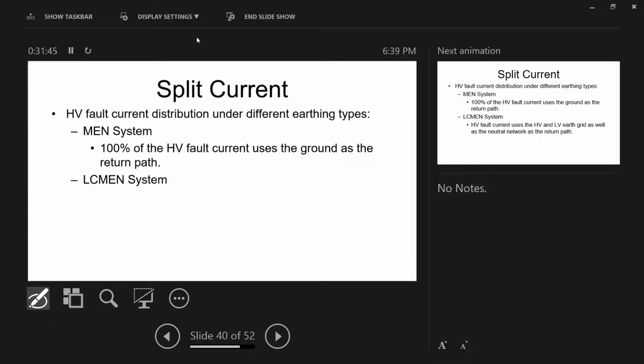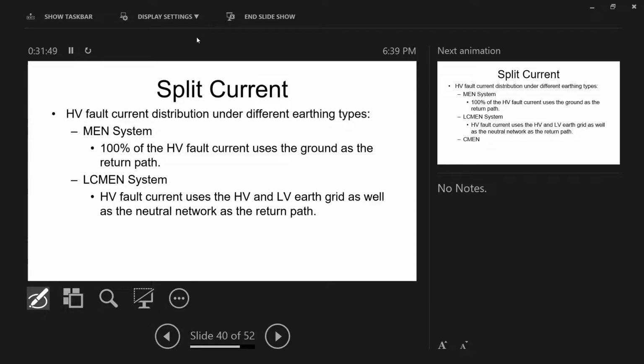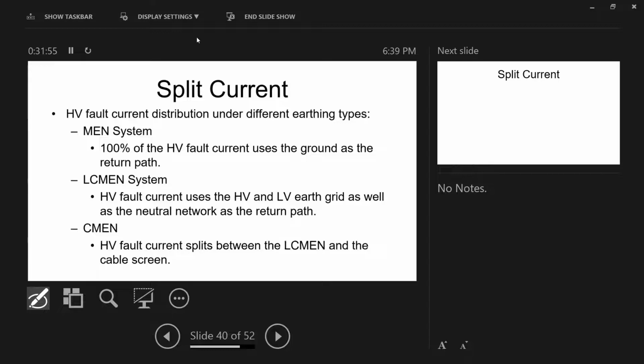You have a local common main earth neutral system. This uses the high voltage and low voltage earth grid. You have a common main earth neutral system, which uses the cable screen.